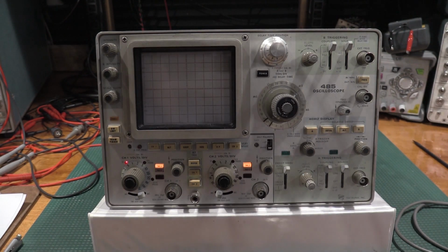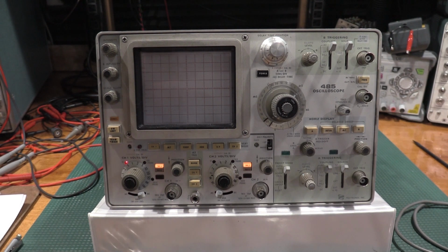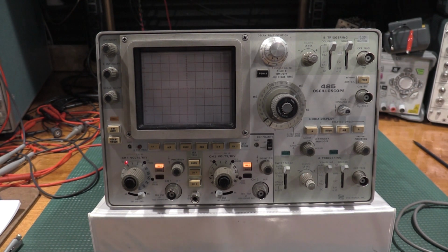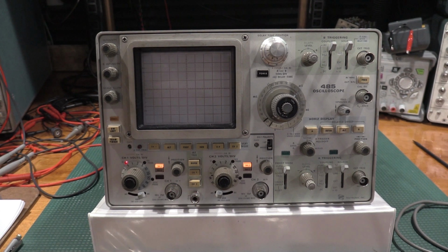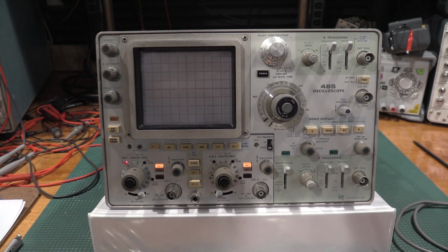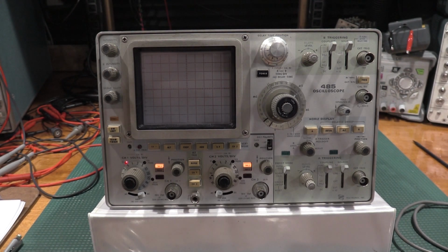In continuing with the series on this 485, we are into the vertical section of the scope. This picks up in the service manual on step 40, starting with checking of the LEDs, and goes to step number 72. So we've got about 30 steps in the vertical, 40 to 72, and we will get started on that.